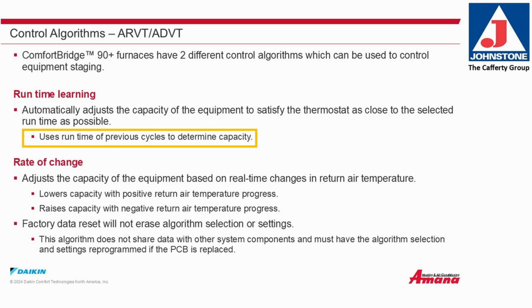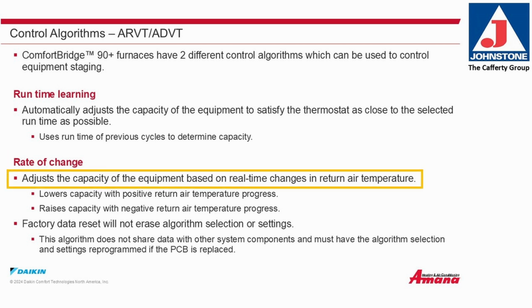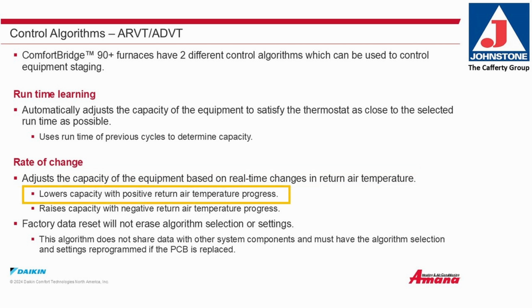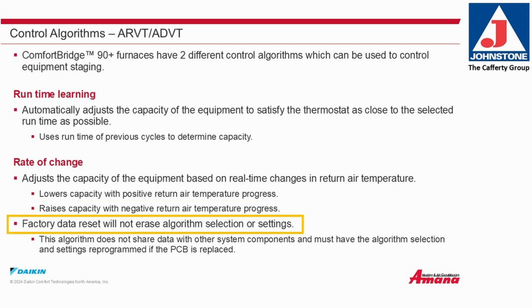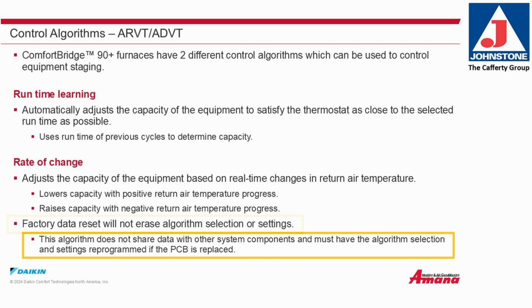Uses runtime of previous cycles to determine capacity. Rate of change adjusts the capacity of the equipment based on real-time changes in return air temperature. Lowers capacity with positive return air temperature progress. Raises capacity with negative return air temperature progress. Factory data reset will not erase algorithm selection or settings. This algorithm does not share data with other system components and must have the algorithm selection and settings reprogrammed if the printed circuit board is replaced.